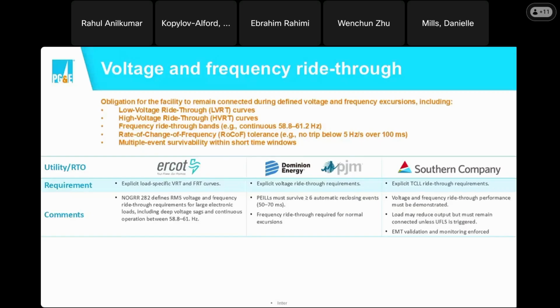They're increasingly being defined with either explicit low voltage and high voltage ride-through curves or frequency ride-through curves. They're also being defined with rate-of-change-of-frequency tolerance thresholds.